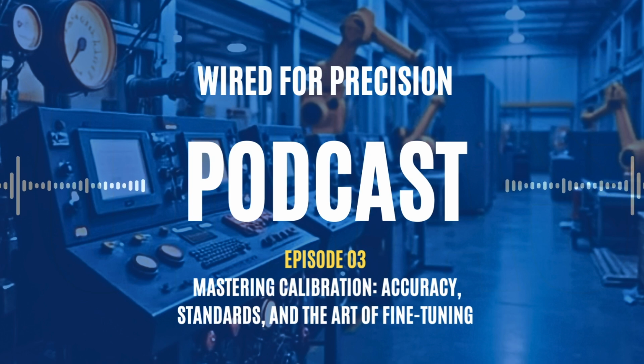3. Dealing with uncooperative instruments. Some devices may be outdated, lack modern communication protocols like HART or Foundation Fieldbus, or show signs of failure. Knowing when to calibrate, adjust, or recommend replacement is part of the job. 4. Environmental extremes. Outdoor calibrations can mean dealing with intense heat, cold, or rain, all of which affect both the technician and the instrument. Portable, ruggedized tools become essential. 5. Human error and inconsistent practices. Without standardized procedures or proper training, calibration data can vary widely. This is why SOPs and competency-based training are so important.